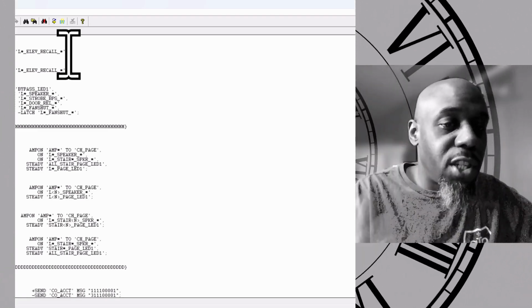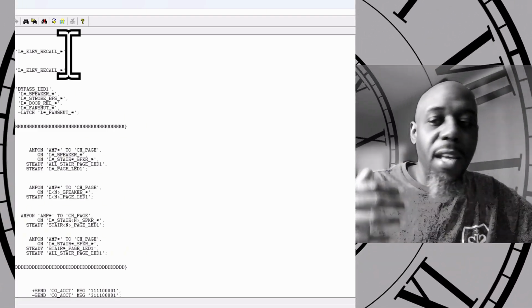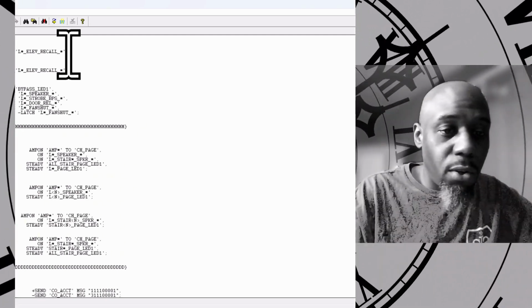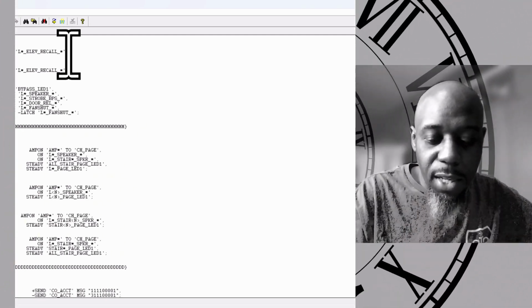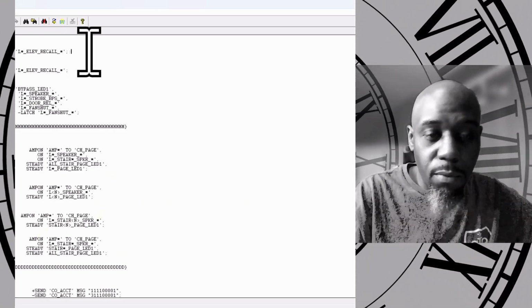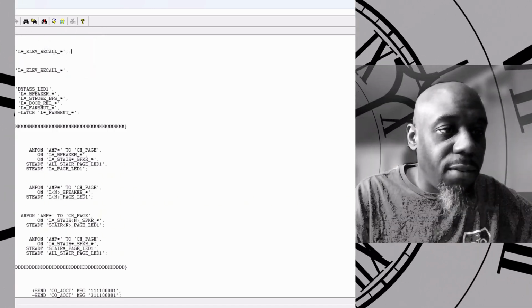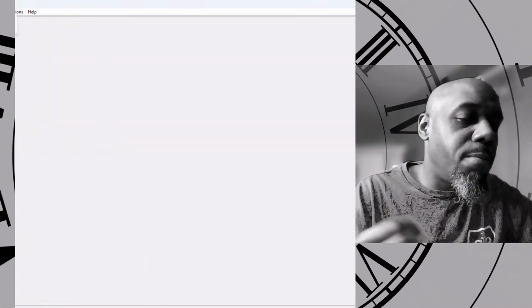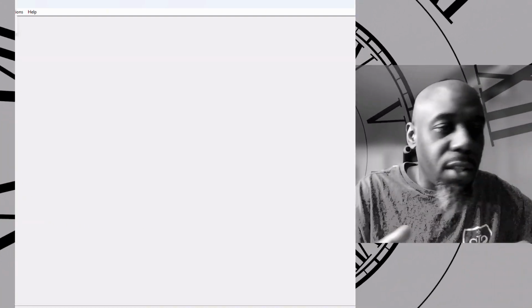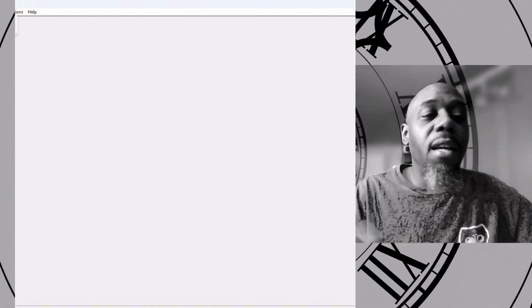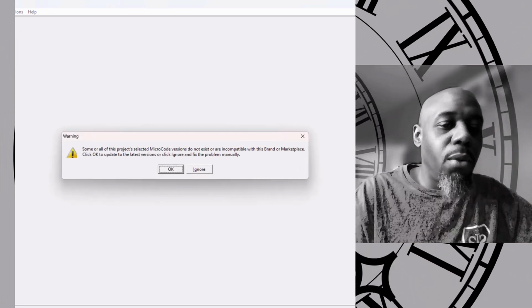And if you don't have a semicolon at the end, it's going to say that you have a syntax error. When you go to try to compile it, you're going to get a rule error. So let me show you what that means. I'm going to erase that, and I'm going to put just a regular colon, and we're going to save that, and then I'm going to close this, and then now we're going to go to rule compile. What compiling is, in short, is briefly taking ABCs, the characters that we see, the stuff that we write, and turning them into zeros and ones, so that way the computer on the fire alarm side can understand what we needed to do. So we're going to hit compile.